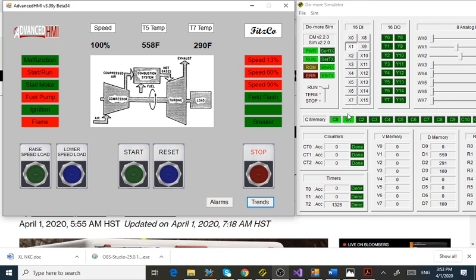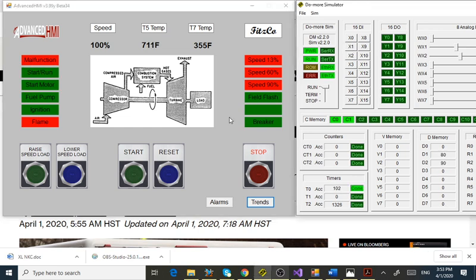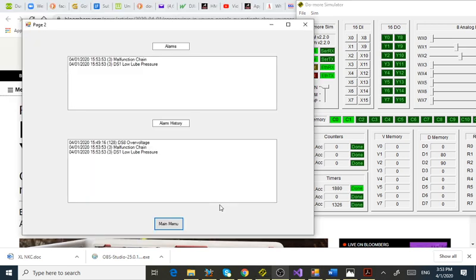Let's trip this unit. Malfunctions are trips, so any trip I put in here will trip it. Let's do a different one — how about X1? All my speed indicators went off, all my devices that run to start are off, and my simulator goes to zero speed very quickly. The cause was low lube oil pressure — that's my X1. I still have my over voltage alarm from 15:49 in the history.